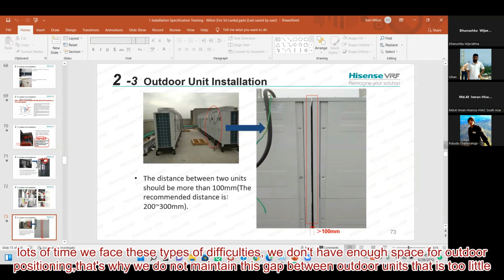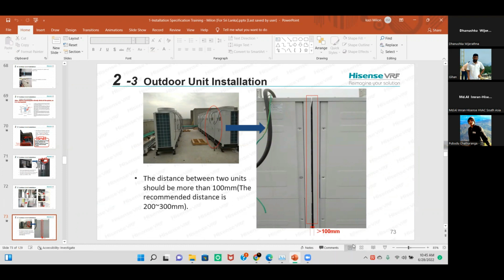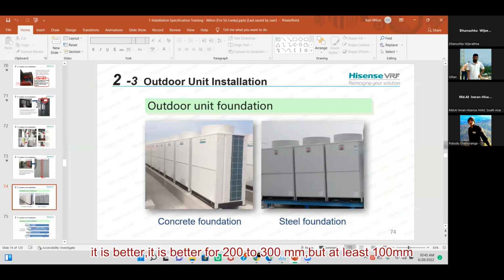We don't have enough space for outdoor positioning. That's why we do not maintain this gap. Here, the gap between these outdoor units is too little. The gap is too little. It should be maintained at more than 100 mm. More than 100 mm is better. It is better at 200 to 300 mm, but at least 100 mm.